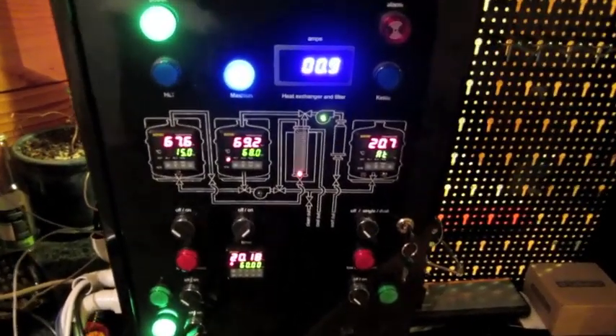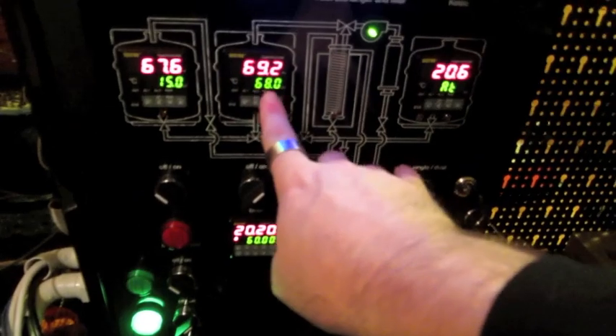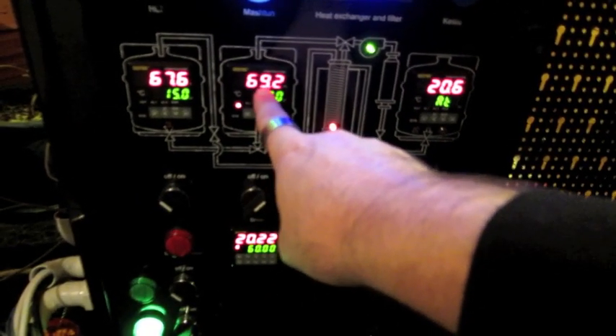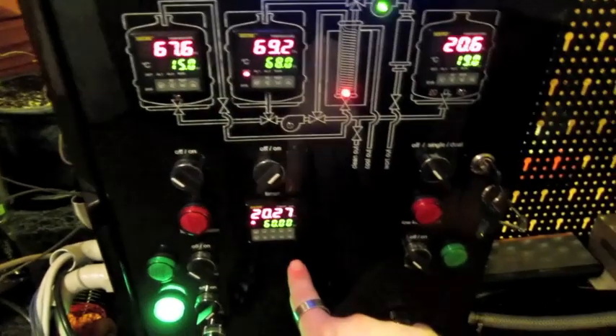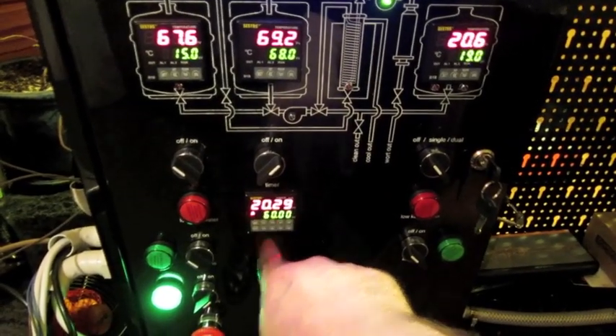Okay, we've reached temperature. PID's overshot by 1.2. But it's done that because we haven't brought this all the way up to the 68 degrees yet. And our time is just on 20 minutes.